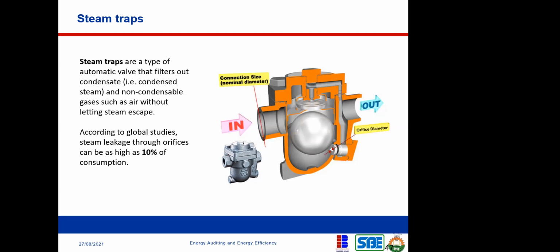So how does it do that? It has an opening. It just opens. So, according to a global study, steam leakage through an orifice can be as high as 10% of consumption. So sometimes this steam trap can open to allow the condensate to go out. Sometimes it can fail to close.